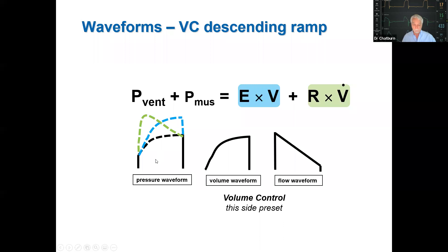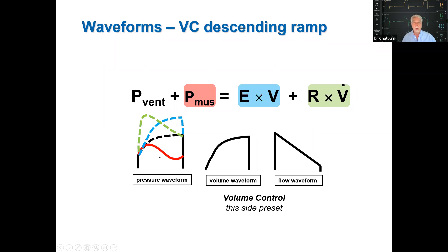If resistance increases, the high flow at the beginning of inspiration hitting a high resistance causes a high initial pressure, and as flow decays, the resistive pressure drops over time. Any increase in muscle pressure will cause a decrease — scooping out — of the airway pressure, because the right-hand side of the equation is constant. This is true of all forms of volume control ventilation.